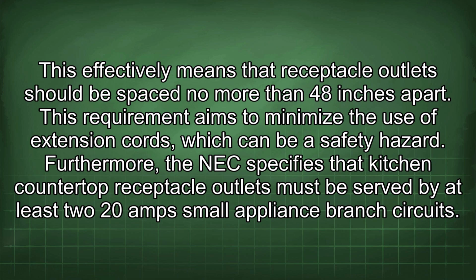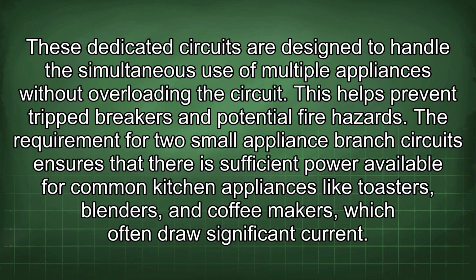Furthermore, the NEC specifies that kitchen countertop receptacle outlets must be served by at least 2 20-amp small appliance branch circuits. These dedicated circuits are designed to handle the simultaneous use of multiple appliances without overloading the circuit. This helps prevent tripped breakers and potential fire hazards. The requirement for 2 small appliance branch circuits ensures that there is sufficient power available for common kitchen appliances like toasters, blenders, and coffee makers, which often draw significant current.